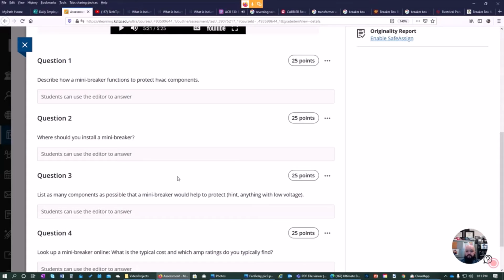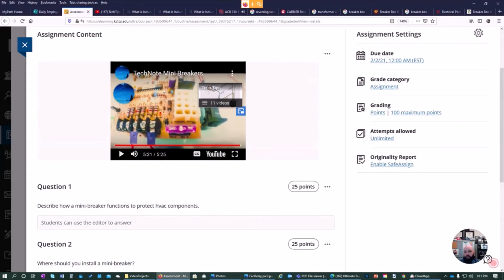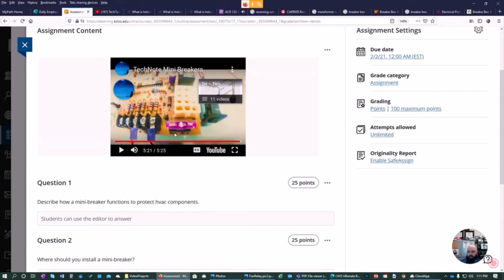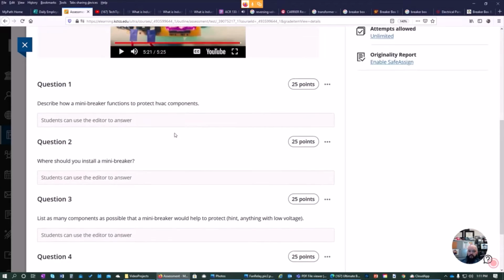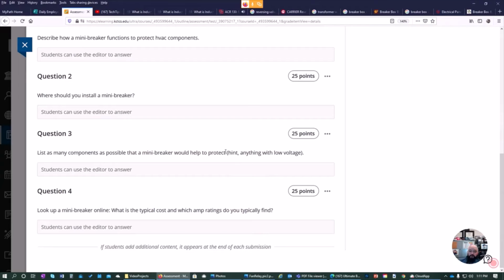it the first time. And if you ever have a situation, say this board burns this high voltage relay into one of these low voltage circuits, without a fuse you're going to burn all the low voltage controls in that unit. What are those components you'll burn? Anything with low voltage. You'll burn the transformer itself. You'll burn the circuit board, indoor, the defrost board, outdoor, or newer units with inverter compressors.